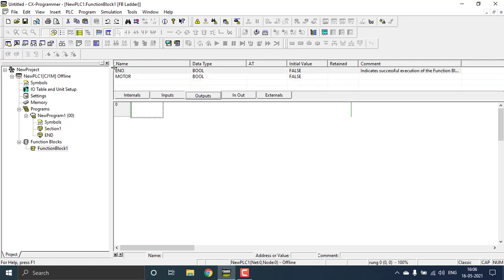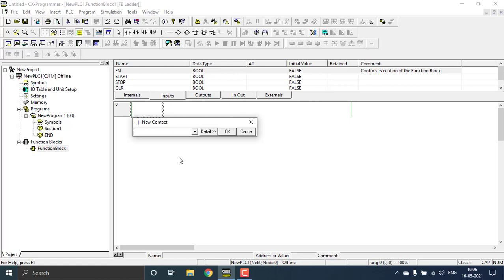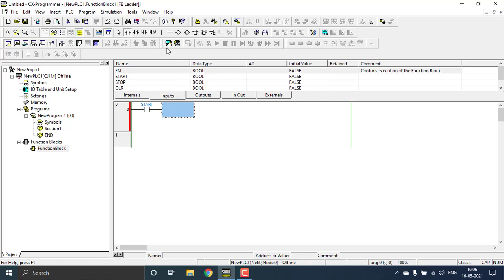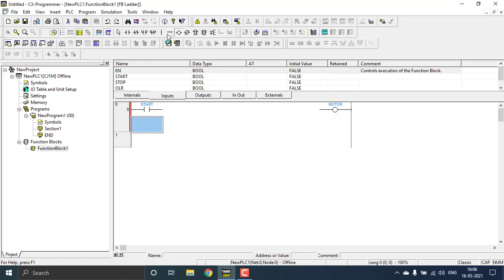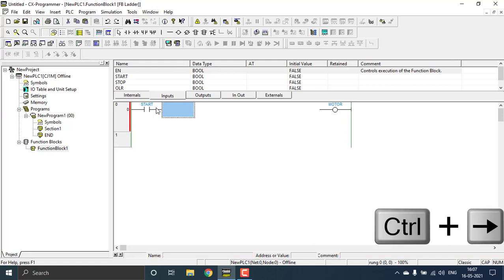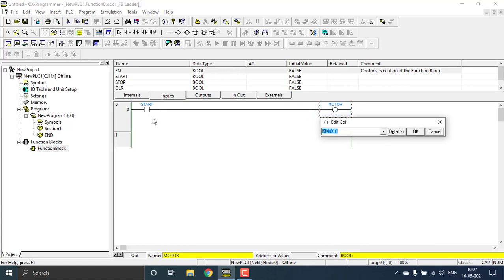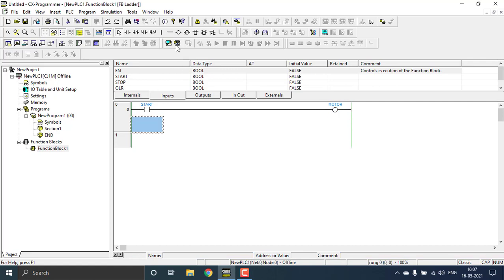Now I am going to create my own logic using the local variables: start, stop, OLR, and the motor output. I place my first contact — 'start' — and name it as start. Then place the motor output coil here, name it 'motor'. To complete the rung, press Ctrl and Right Arrow — that will complete the rung.